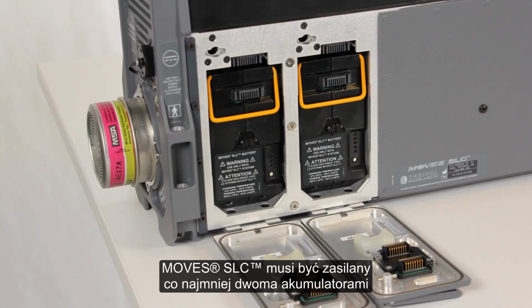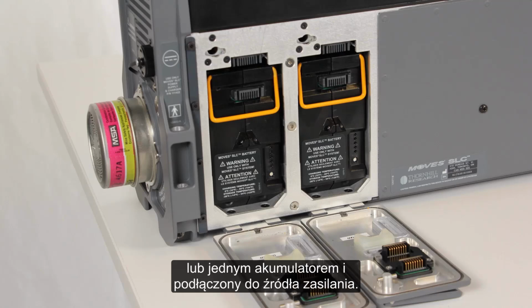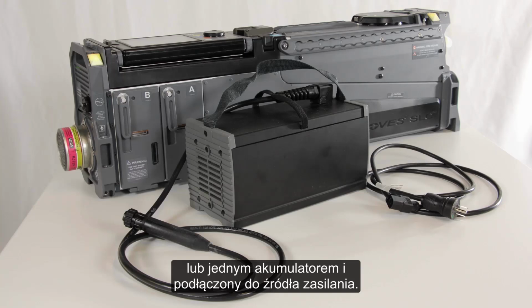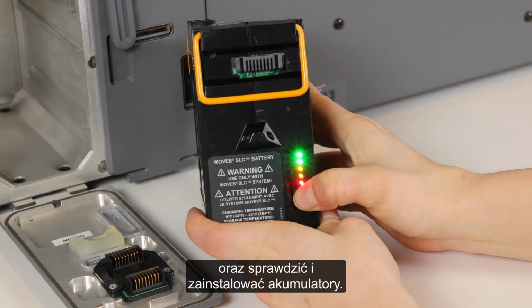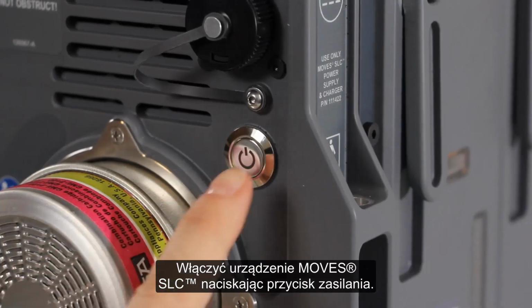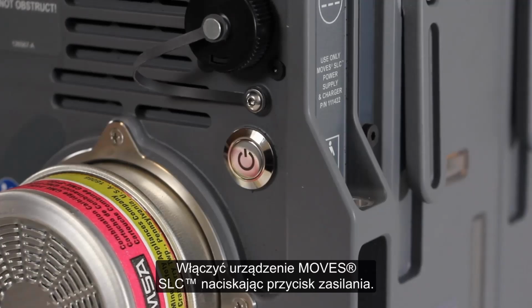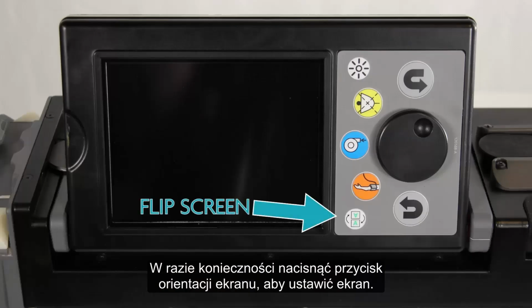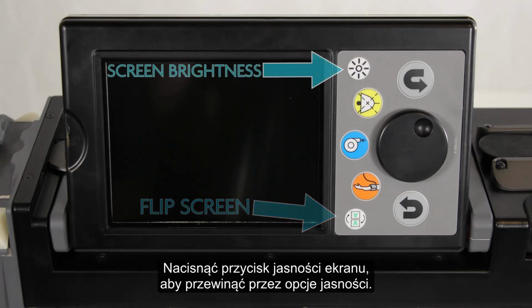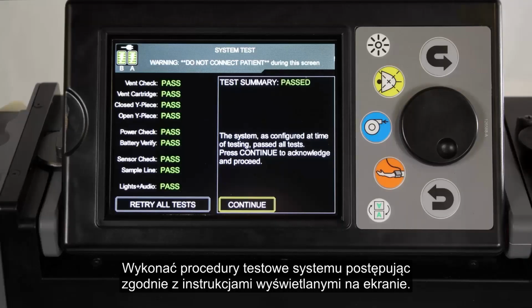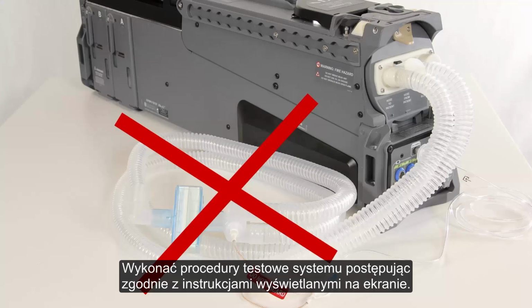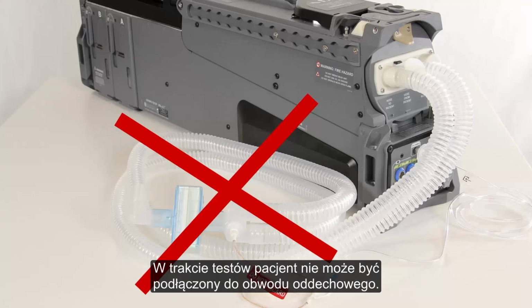Moves SLC must be operated with at least 2 batteries or 1 battery and connection to the power supply. As required, connect the power supply to the Moves SLC and inspect and install the batteries. Turn the Moves SLC unit on by pressing the power control button. Press the screen orientation button if necessary to orient the screen. Press the brightness button to cycle through the brightness options. Perform the system test procedures by following the on-screen instructions. The patient must not be connected to the breathing circuit during tests.